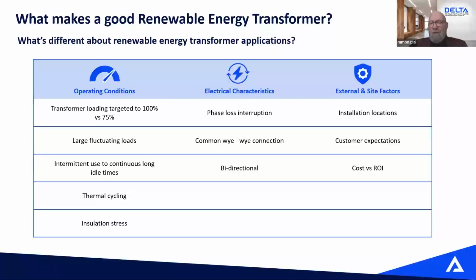Lots of stress on your dielectric insulation system, depending on the type of system and the type of inverter, those switching transients. The transformer needs to be built in such a way that the inverter can figure out if there's a phase loss, either on the grid or on the generating side. Usually, we're going to see some very odd or special types of winding configuration, YY being one of the most common winding configurations we see in renewable energies.